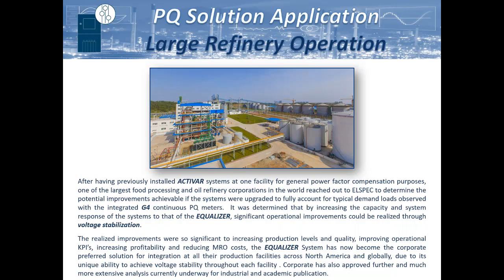or they're just looking to get rid of power factor penalties. We also have another model called our ACTIVAR, which has the same exact internal components. There's no differentiation in performance or functionality, with the small exception of the total response time. The ACTIVAR is more comparable to a traditional capacitor bank system, but with much better response time. Instead of a single step response every 20 or 30 seconds, we can do full load demand response, typically between 1 to 2 seconds, with a maximum time of 3 to 4 seconds.